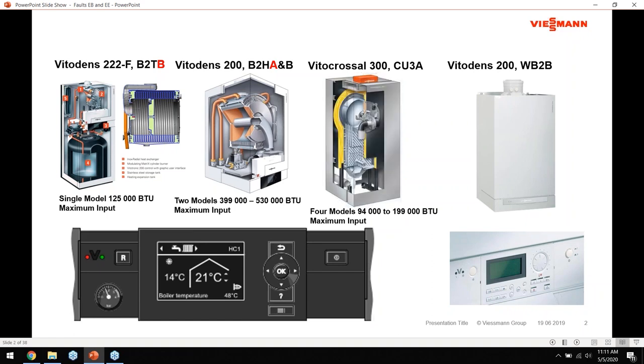Moving over to the CU-3A - in my opinion, more of a throwback as far as boilers go. You'll need to dust that dolly off installing these - it's a hefty boiler as far as size and capacity. Just like older atmospheric cast iron boilers, this is a high mass unit, which really helps with burner cycling issues. It has the benefits of high mass combined with condensing and modulating burner operation - the best of both worlds. It has four sizes from about 94,000 BTUs up to 199,000 BTUs maximum input.